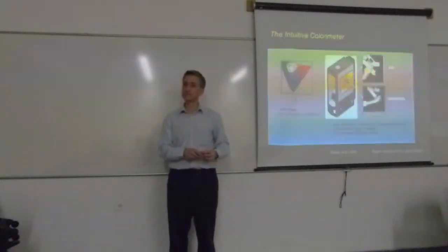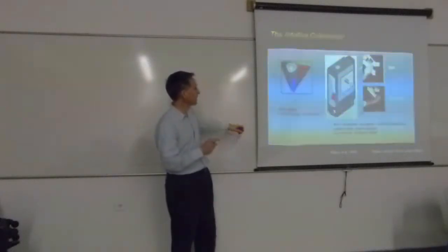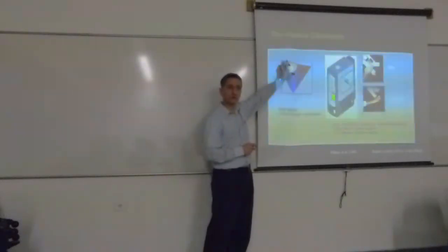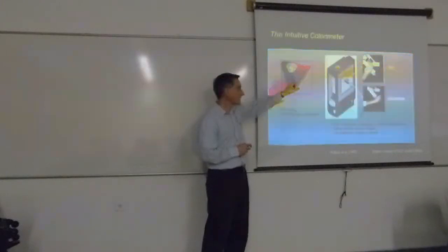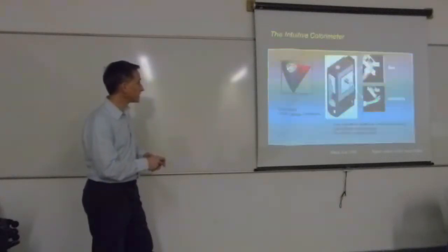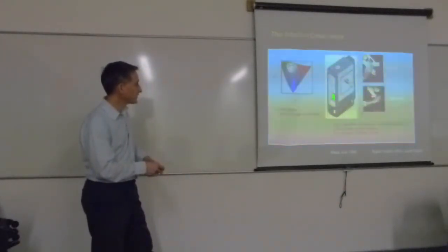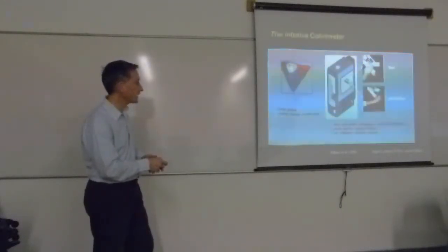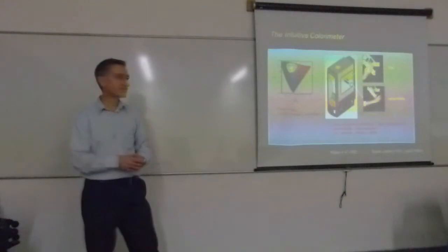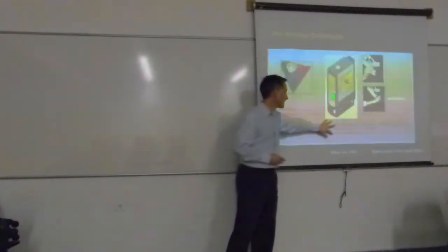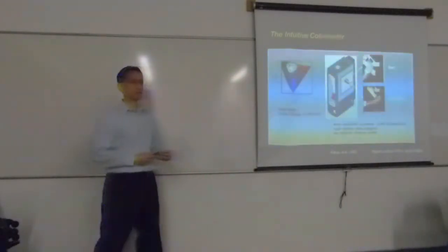and these controls are adjusted by the optometrist to change the colour of that light. And the way those controls work, the way the colour is changed, is to explore human colour space within the triangle of human colour perception. So you have three controls here. One control changes the hue, so it goes around in a circle. This control here, that one, changes the saturation, the depth of colour. And the third control, just up here, changes the brightness. It's got a very large gamut of colours, and you can independently vary hue, saturation and brightness.